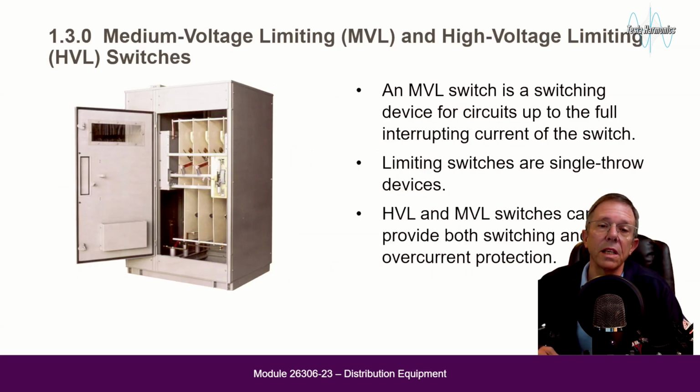Medium voltage limiting and high voltage limiting switches. An MVL switch is a switching device for circuits up to full interrupting current of the switch. Limiting switches are single throw devices. HVL and MVL switches can provide both switching and overcurrent protection.